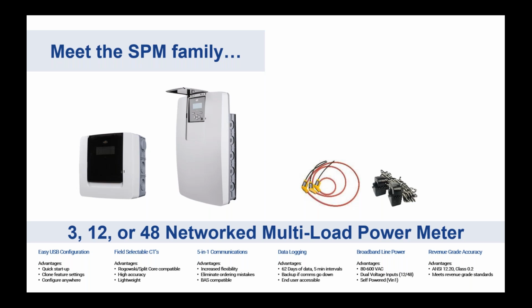So the 3 and the 12 are on the left side image, and to the right of that is the 48 load meter. That'll be a little bit larger enclosure to accommodate the extra CTs, as well as give you room to land some wiring in there. As you have more and more loads and are measuring more and more things, unfortunately you need more and more space for wires that are going to go in there. So we try to accommodate that within our package based on some feedback from people out in the field.